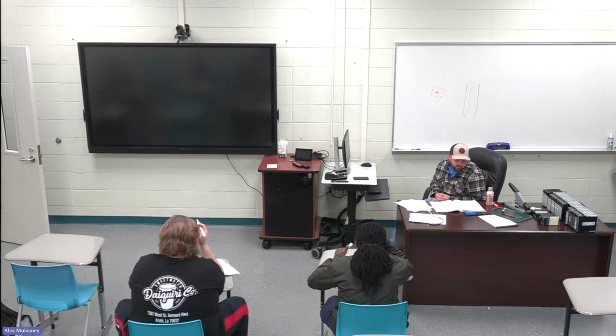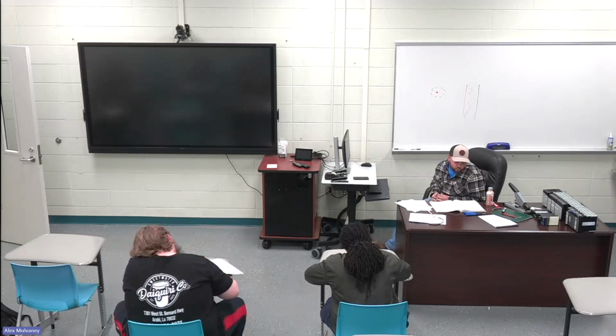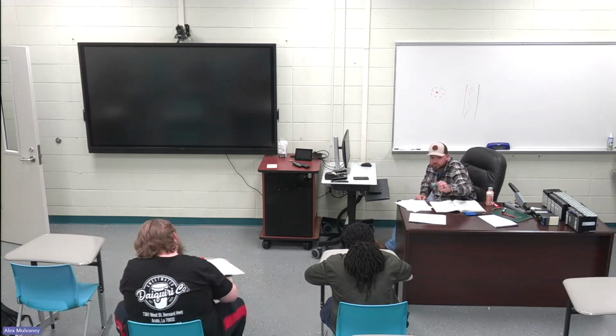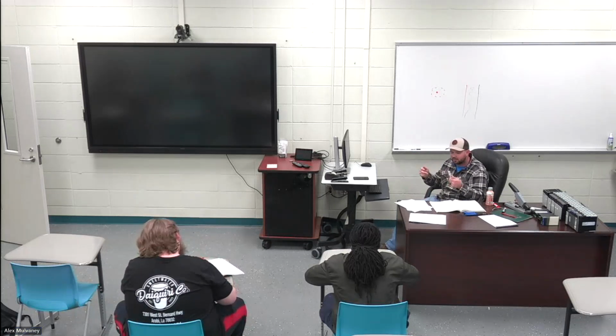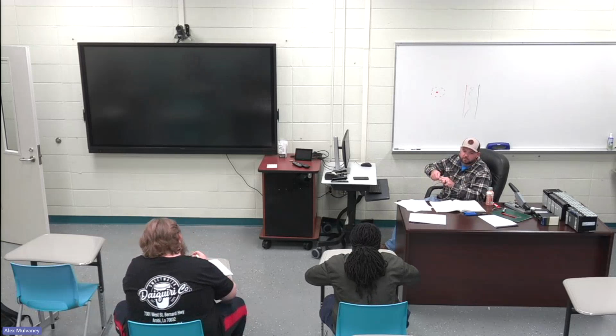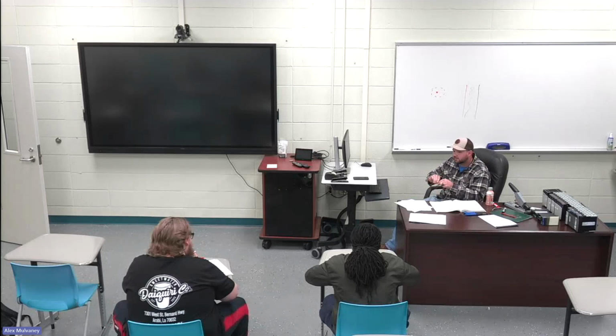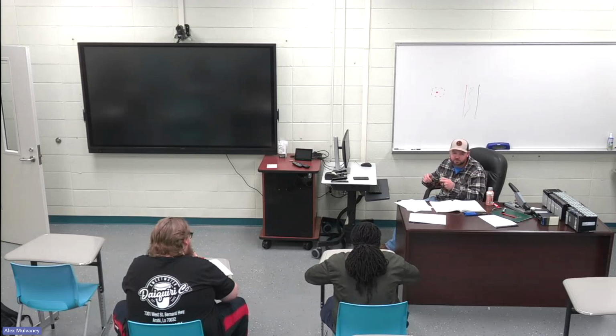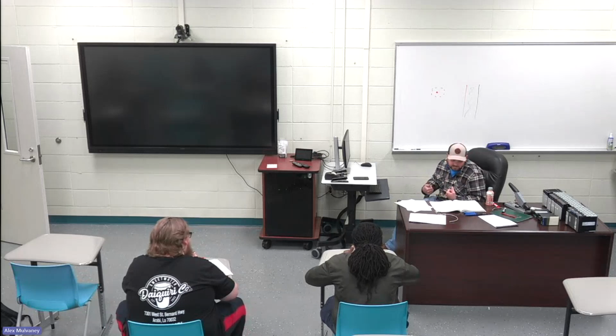Shield termination. First sentence is an online test question. Shield quality is usually compromised at the termination point. Usually when you're terminating this, you can use your drain wire as a shield, but you also have to terminate this. Usually what I do when I'm terminating this stuff is twist it up as much as I can. If you've ever wired a plug or anything like that, you have a ground terminal and you make a little hook. You can imagine that would be the best electrical connection there is. Sometimes you might want to loop it twice, but they're just saying that is the biggest source of where quality is compromised when terminating a shield.